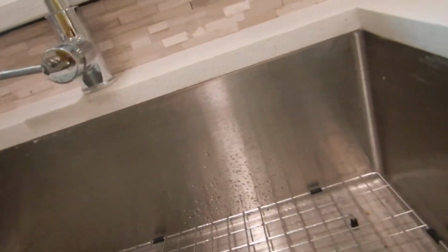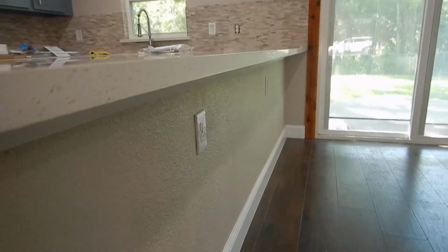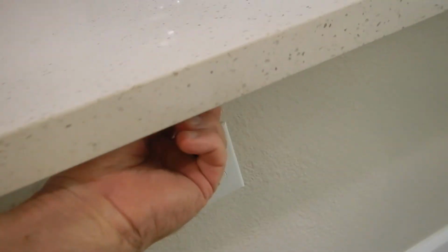And a couple other things. There we go. And we'll just move on along right in here. When you have an overhang like this, and these are GFCI protected, by the way, it's not supposed to overhang more than 6 inches. This is about 7 inches. Okay, now it's a relatively recent code. I mean, it's like 2015.